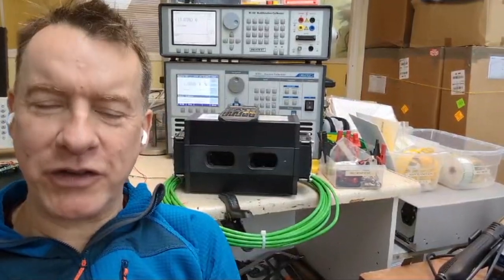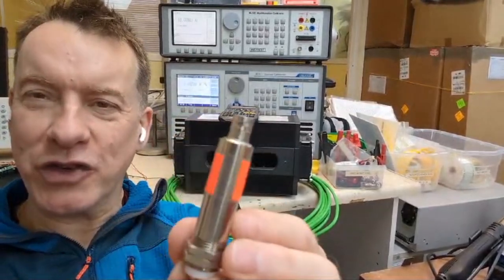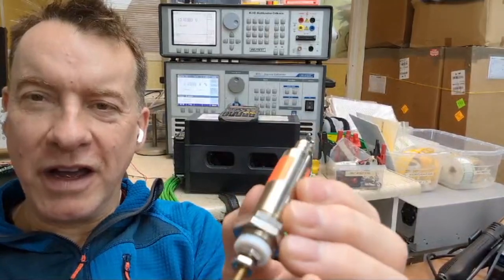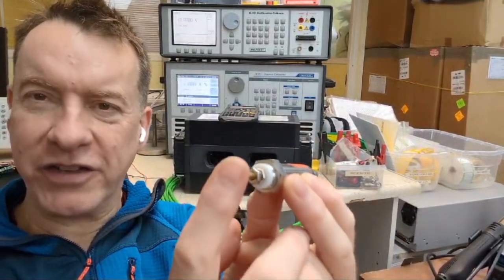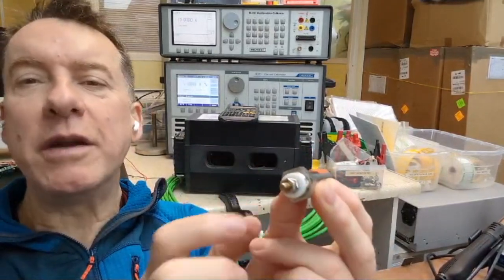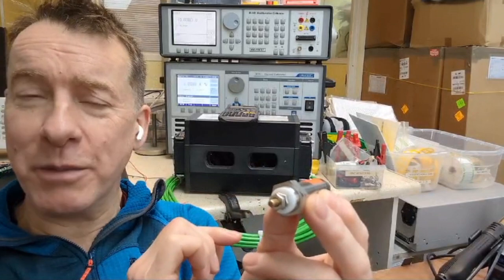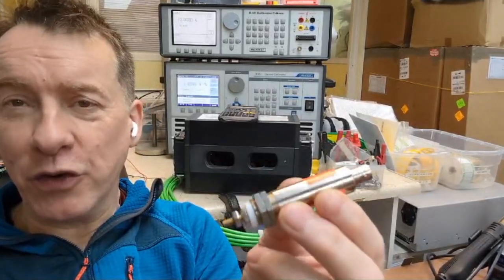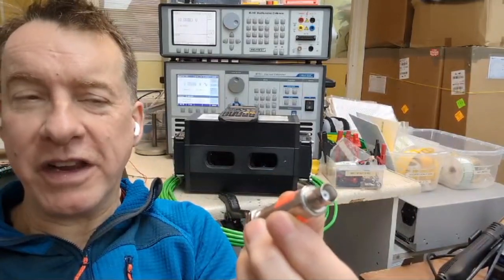This short episode is just really to introduce coaxial shunts. And here we have a coaxial shunt. For those that have not seen these devices before, here's the business end where the current would go in, for example, into that stud, and then it would return back down the barrel after going through the current measuring element and then into your PCB, your circuit. And then, of course, the output voltage would come out of that BNC.